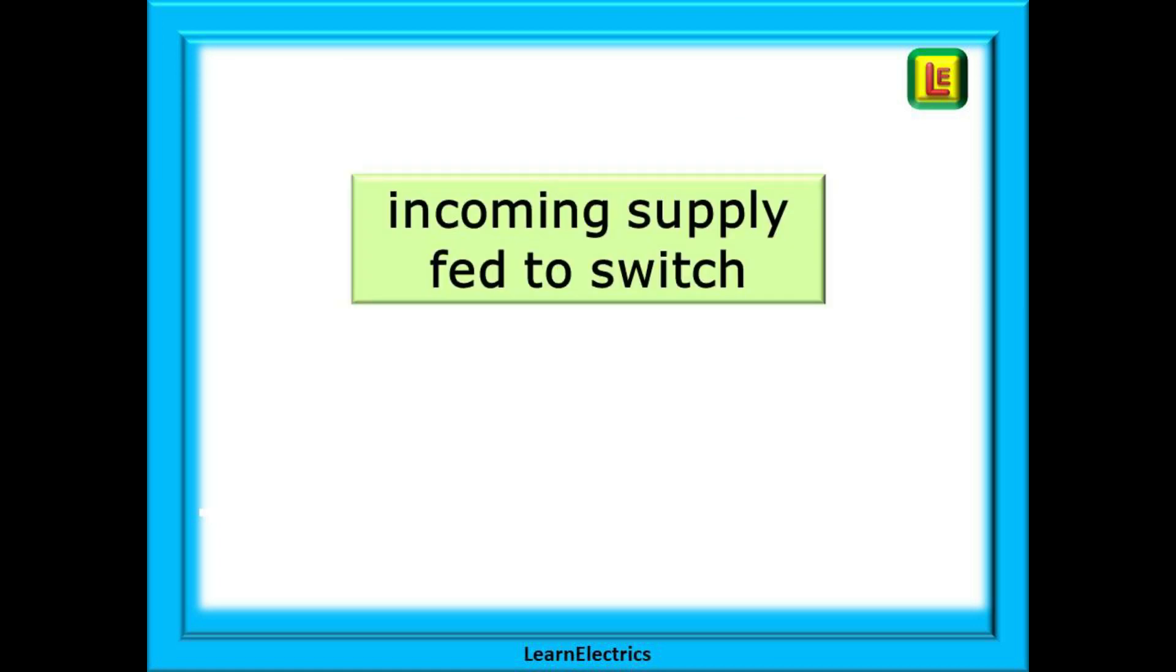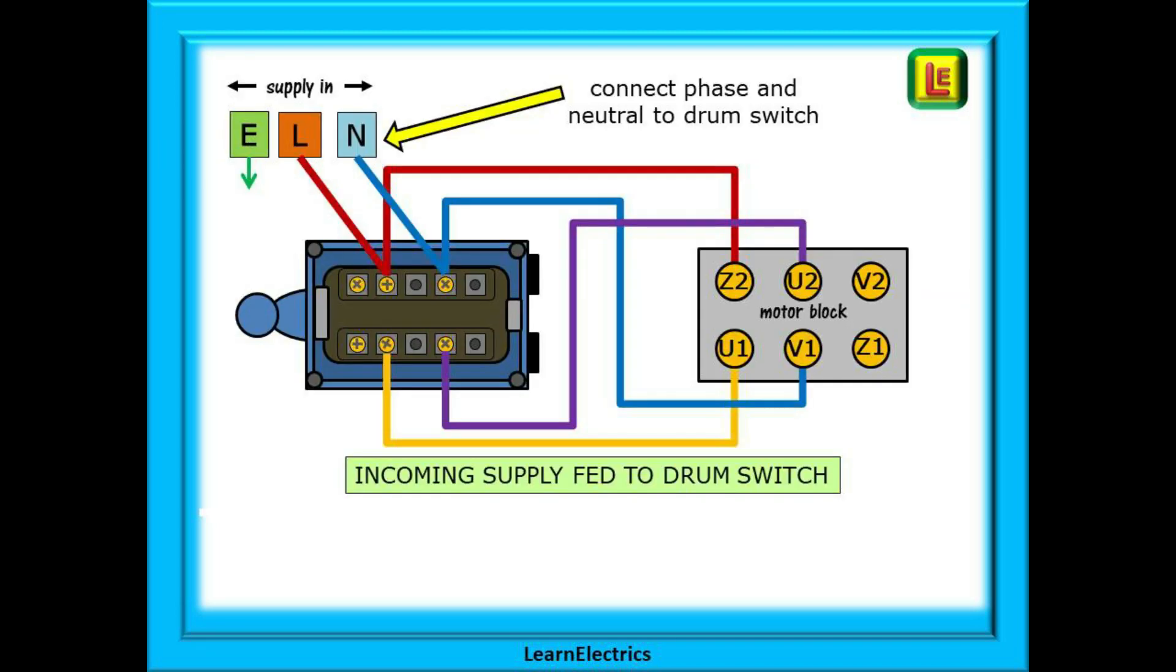We can also consider now two variations that are very easy to do. First how would we wire up the drum switch if the motor and switch were both part of a new installation and we wanted to take the incoming supply straight to the switch and not the motor. Now we will connect the incoming phase to contact number three of the switch in our example and the incoming neutral to contact number seven of the switch. Don't forget to take the earth to the switch and to the motor.